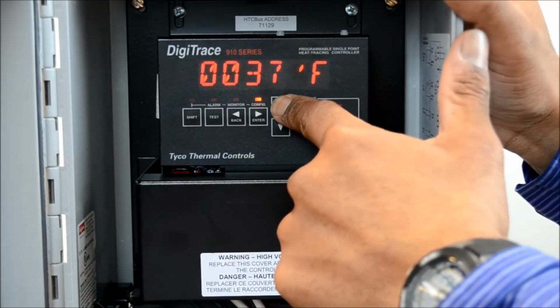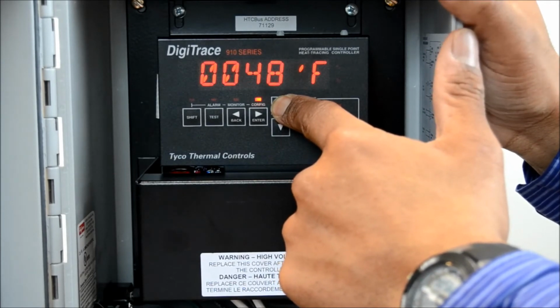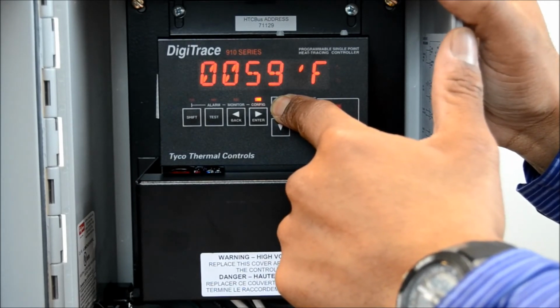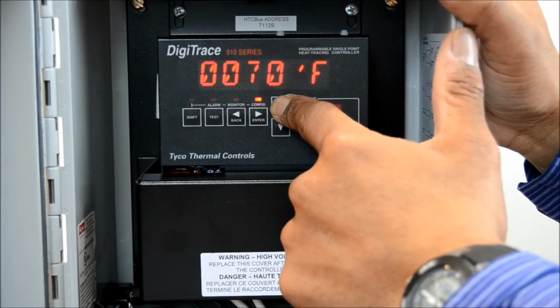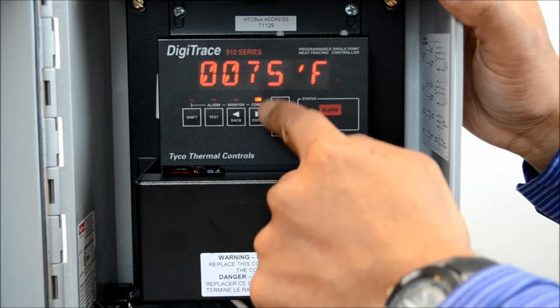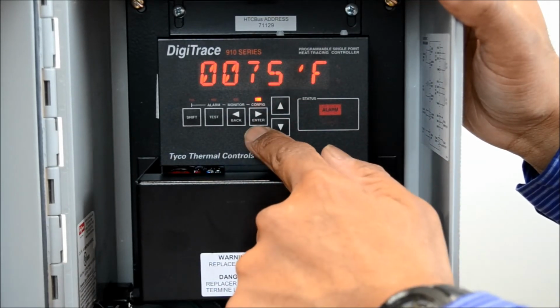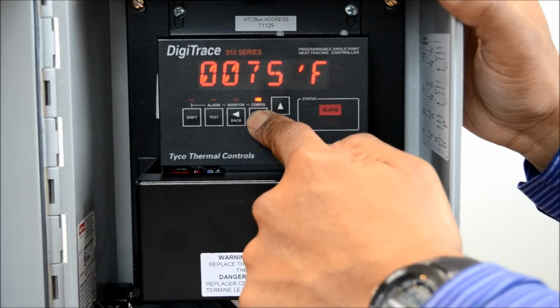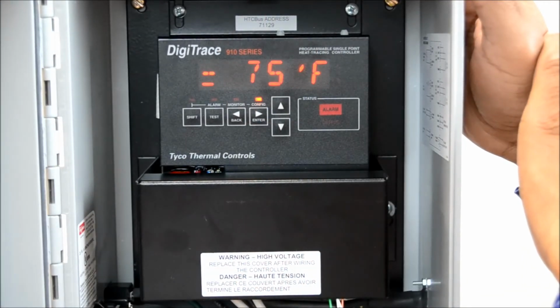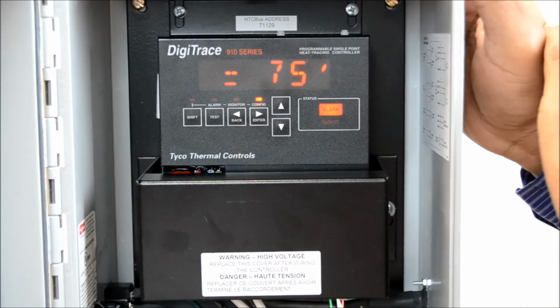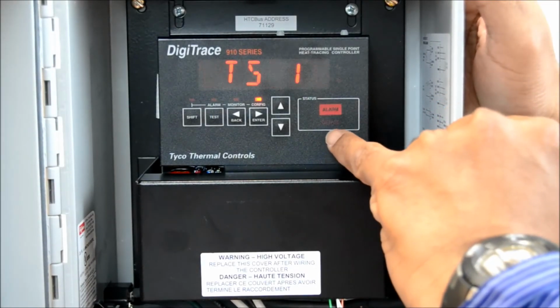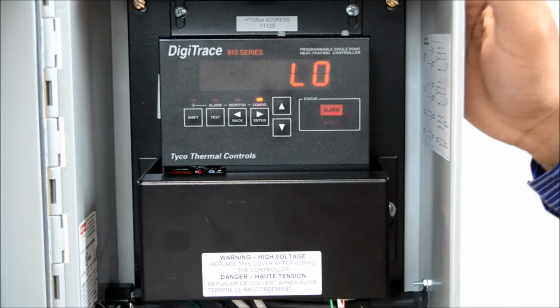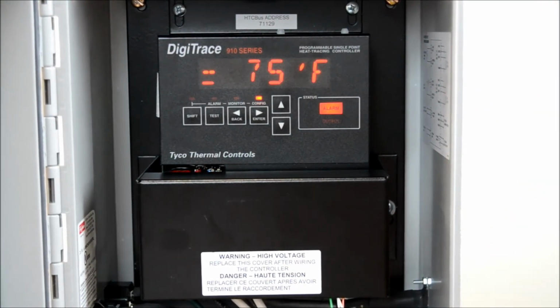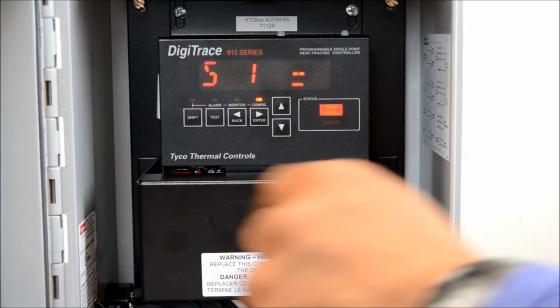Since it's a little warm in the room, I'm going to go all the way up to, let's say, 75 degrees for the low temperature. And I've already set the low temperature alarm. Now it's at 75 degrees. It's still blinking, so I'm going to hit enter and see what happens. Okay, now you can see the alarm light just popped on and it's flashing. The reason for this is because I set the low temperature alarm at 75 degrees and the room temperature is only 60 plus degrees.